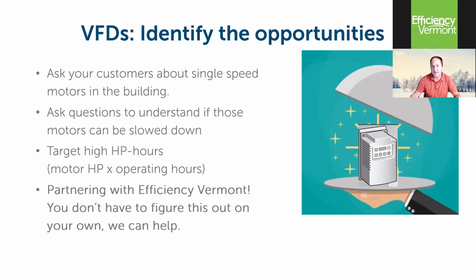We target high horsepower hours, and what I mean is, I'd rather go after a 5 horsepower motor that runs 5,000 or 6,000 hours a year than a 100 horsepower motor that runs 5 hours a year. Hours are everything. You can save a lot of energy, but you're only saving it in the hours that the thing runs. So don't waste your time hunting down very sparsely used pumps and fans. Go for the heart of the HVAC system, the bigger pumps and fans.